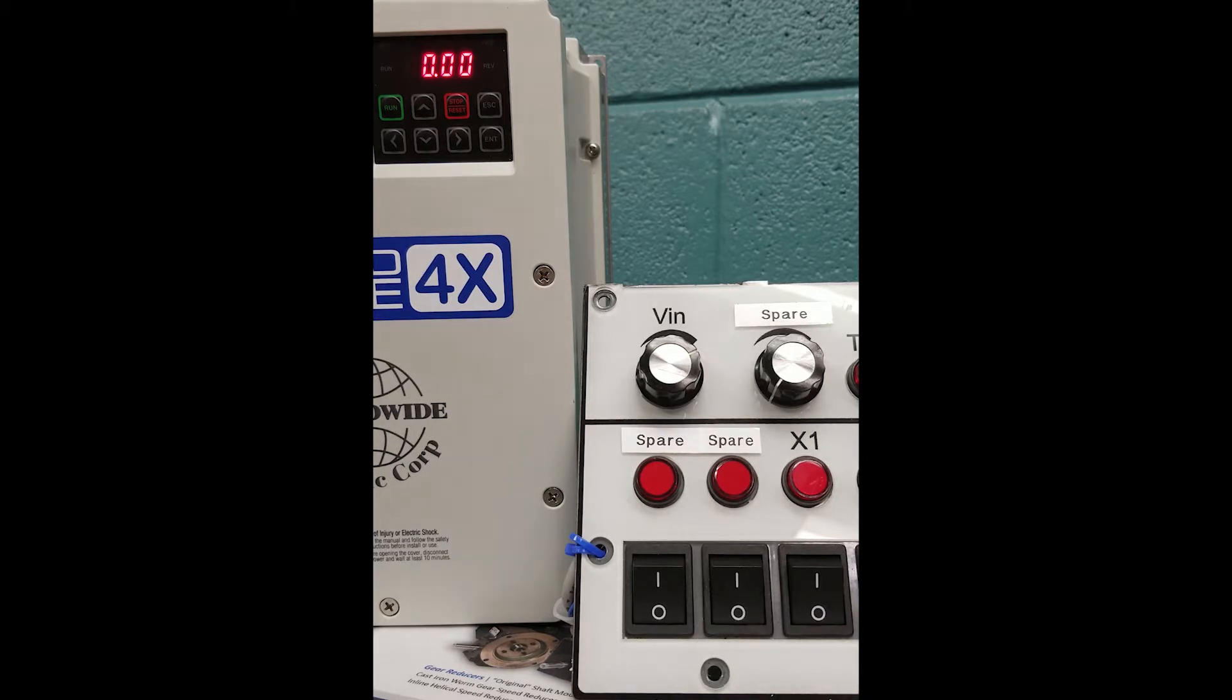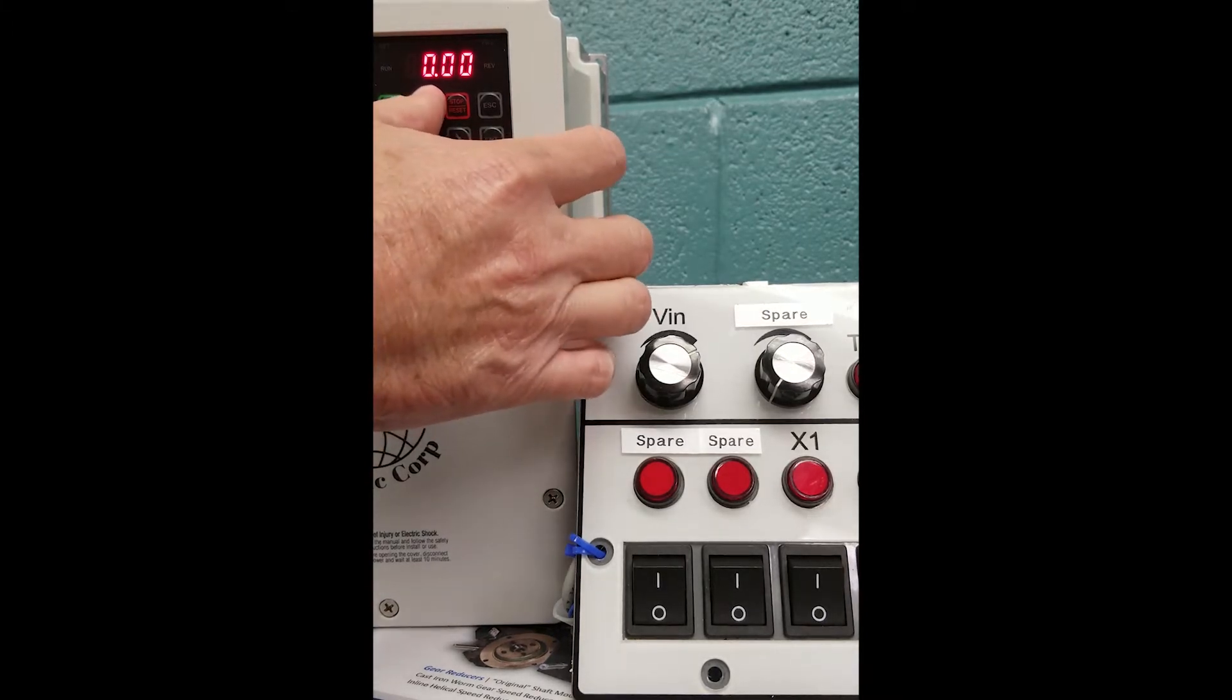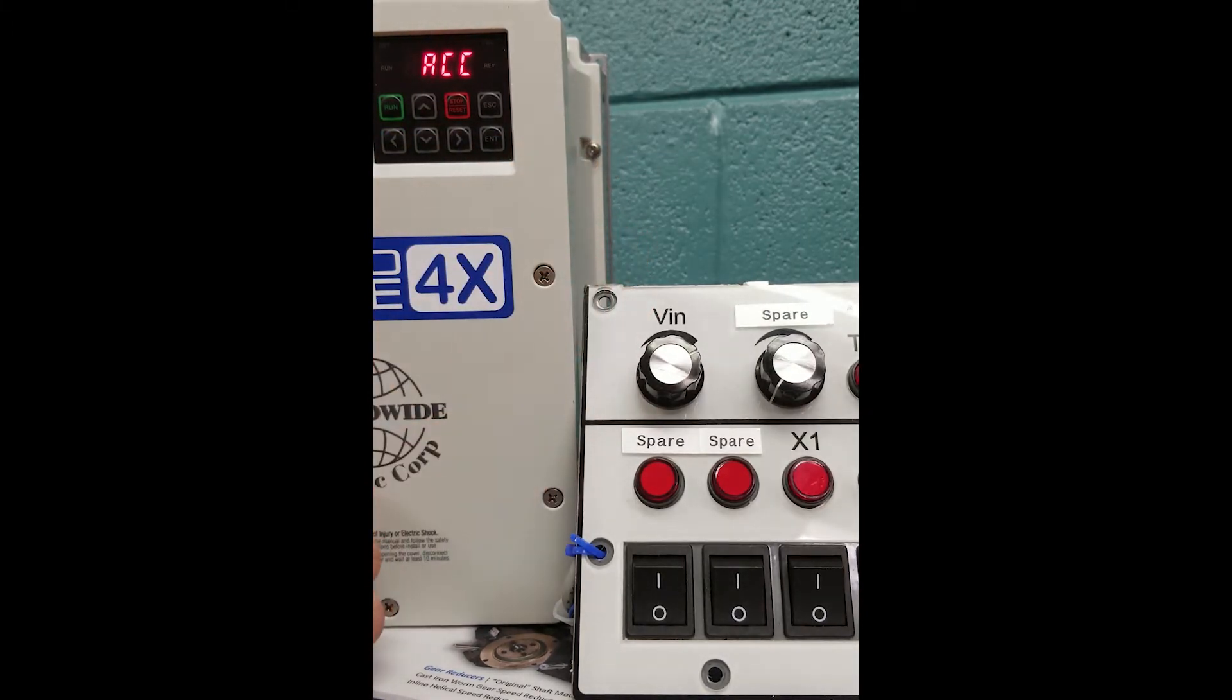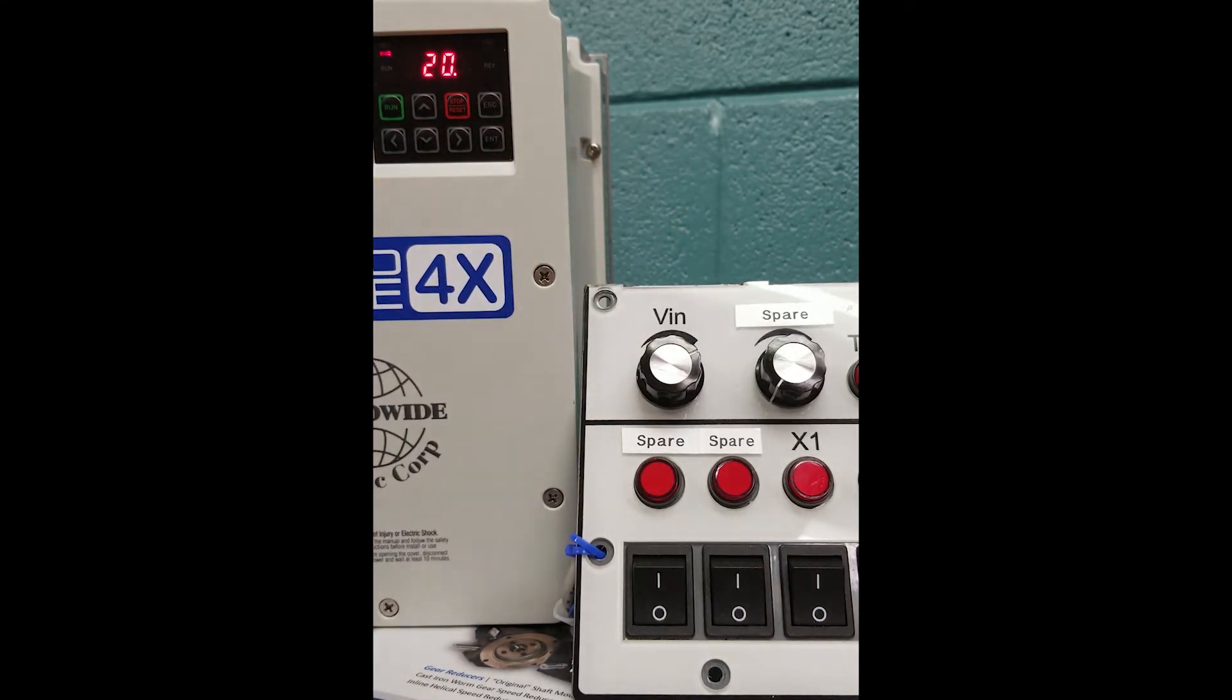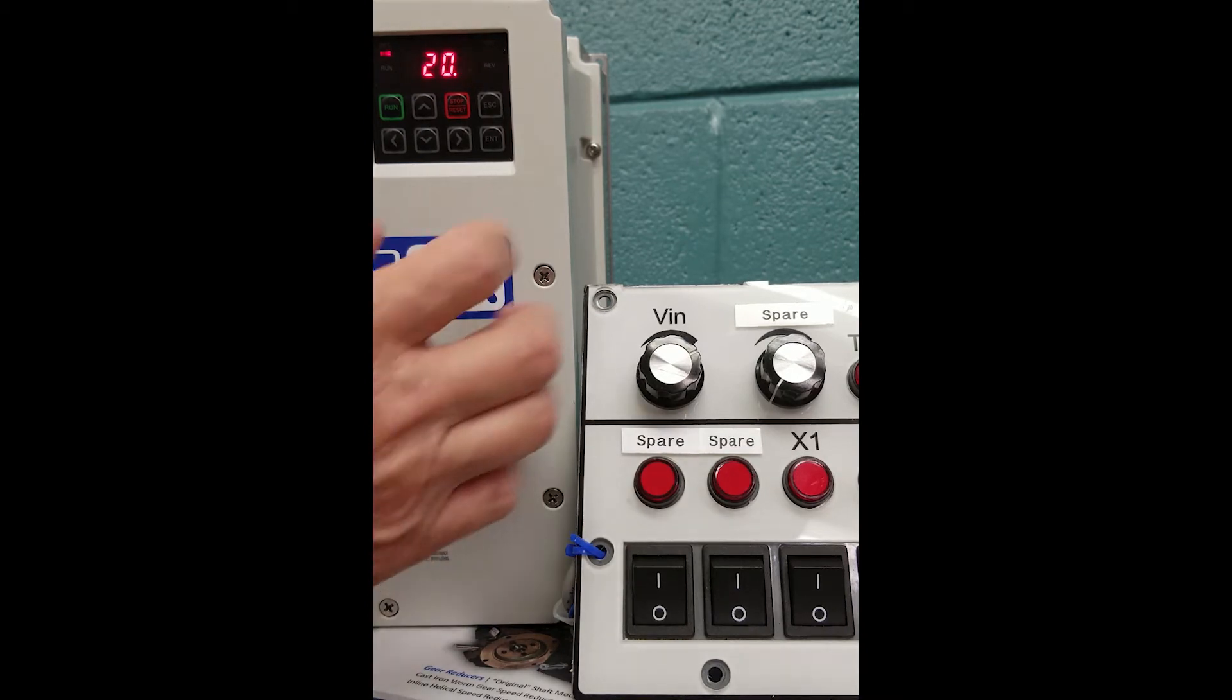Now we will begin our programming. To do so we must hit the up arrow to see ACC to set our acceleration time. We will enter into our ACC, factory default at 20 seconds on this VFD. We're going to change that to 5 seconds.